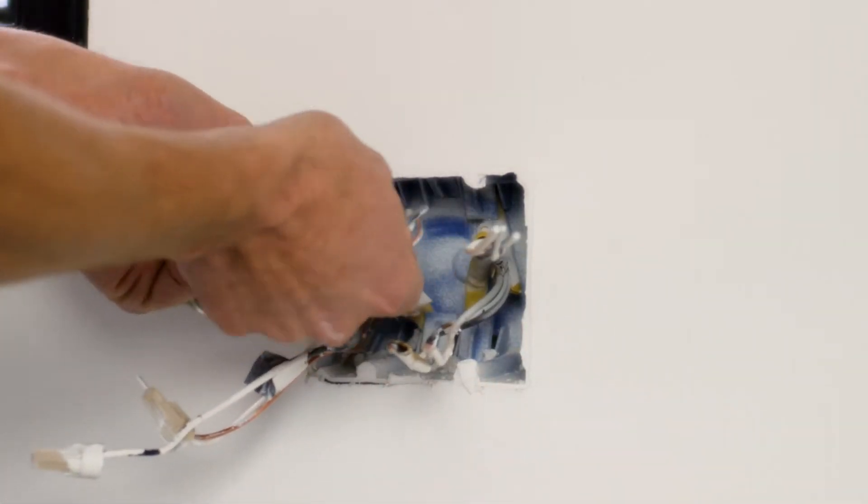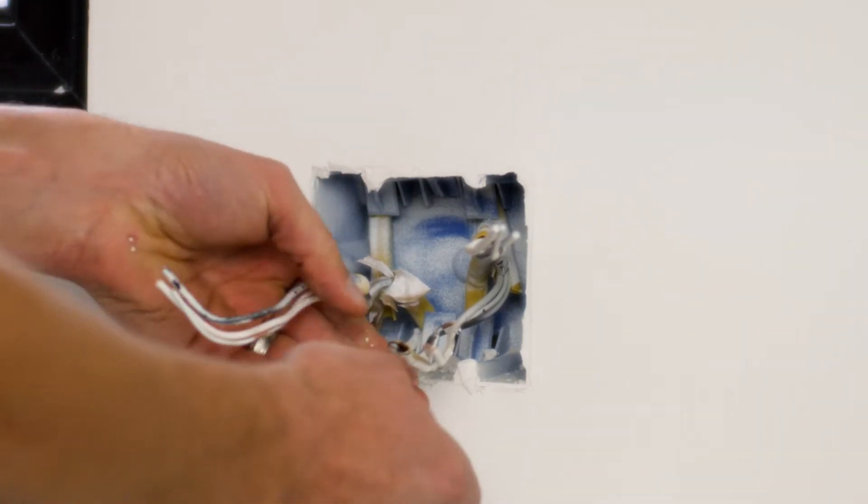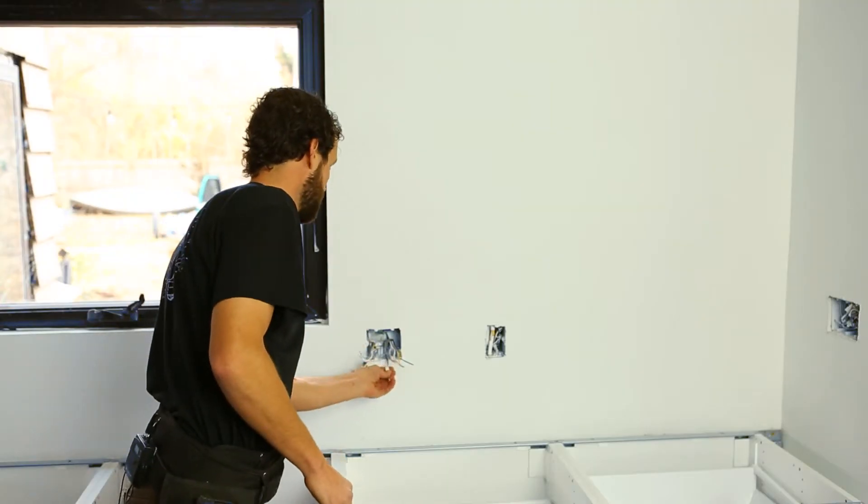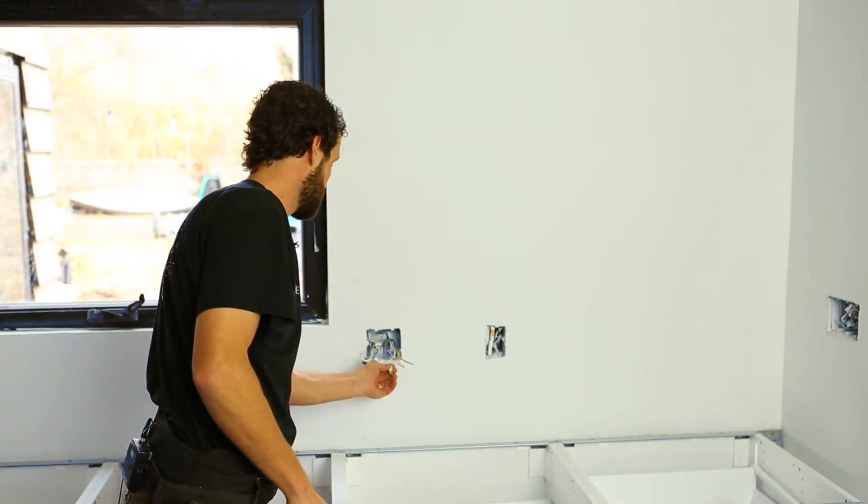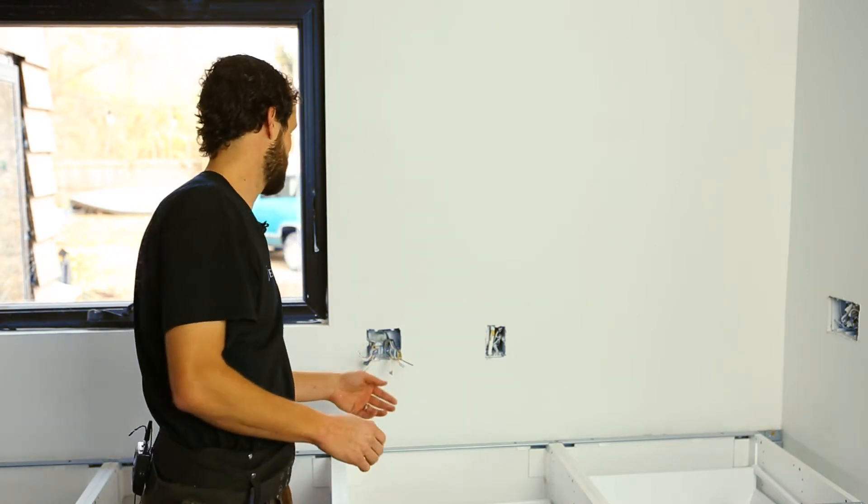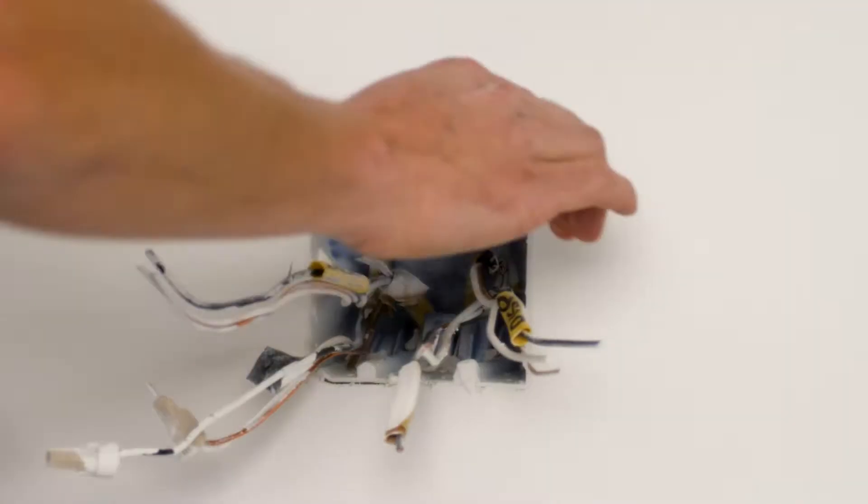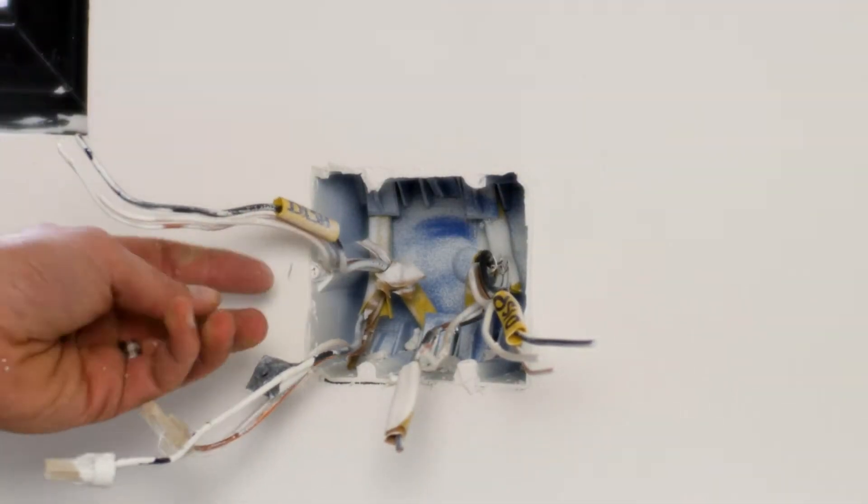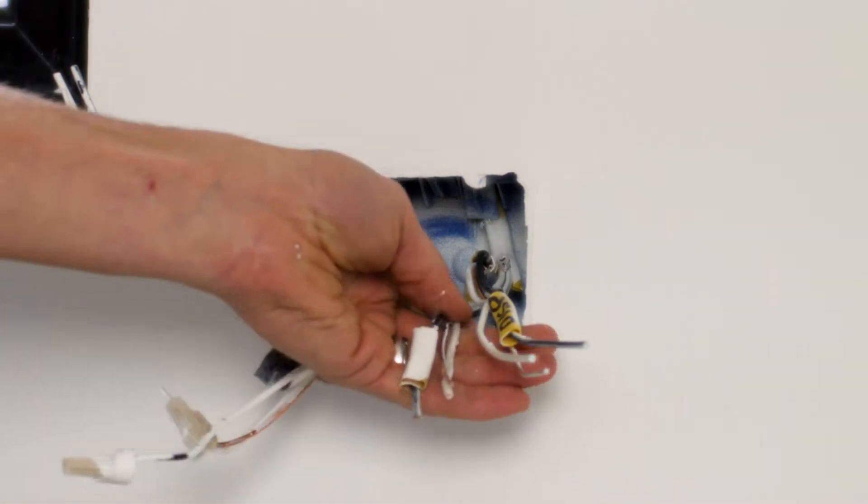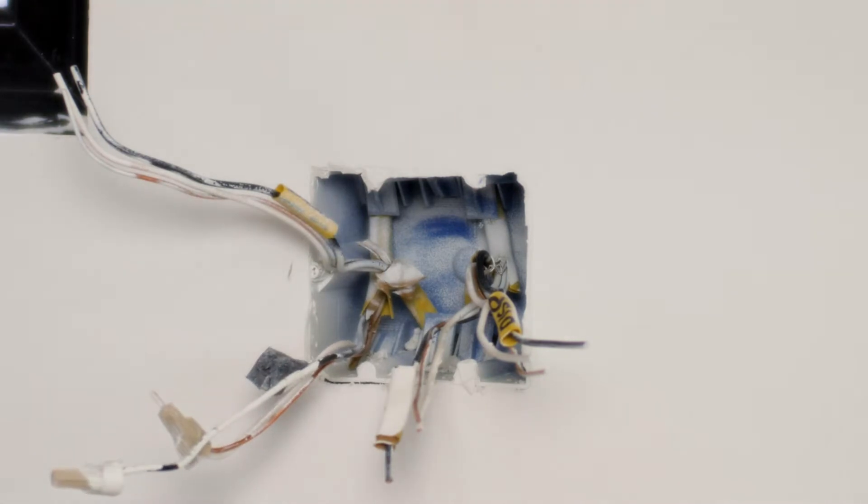All of the rest of these sets of wires are labeled. I have a disposal here, and then one thing that we always run into is this one label I can't read. I tried scratching out the paint with my fingernail, but it won't come off. So I've got a disposal, I've got a dishwasher which is gonna require a hot feed, and then I've got my other switch leg. There's only one purpose left for this wire, so I know what purpose it's performing.